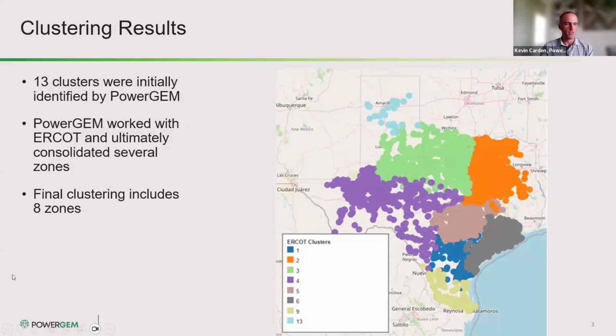Here's a visual of the results of that analysis. You can see we have 8 zones shown here. Since we're using Terra to identify this, it's really the electrical proximity of each node rather than geographical or by ownership. This represents where we expect to have transmission constraints. We've grouped these nodes in a way that should give us the best representation in a zonal model of the actual transmission system's impact on reliability.